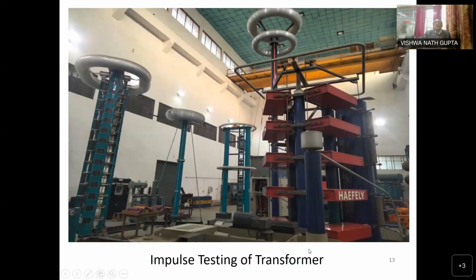This is, sir, our impulse testing laboratory in Ghaziabad. We use it to test distribution transformers and power transformers. If lightning strikes an installed transformer, this equipment tells us whether that transformer is able to withstand the lightning or not. So by this equipment and these operators, we are able to determine the health of the transformer.